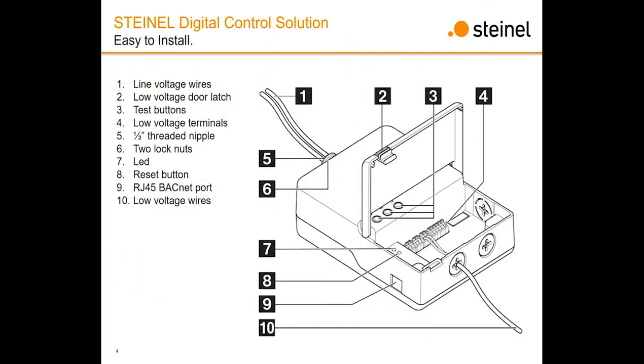You'll notice here just a brief picture of the DCS. So we have the line voltage wires and the low voltage wires actually separated. So the 0 to 10 volt is not bound to that relay. So we can easily switch that 0 to 10 volt in field using the stab-in terminals on the low voltage side. You'll notice it actually mounts via a 1/2 inch threaded nipple with 2 lock nuts. And then it has an RJ45 BACnet port for the DCS Connect version.